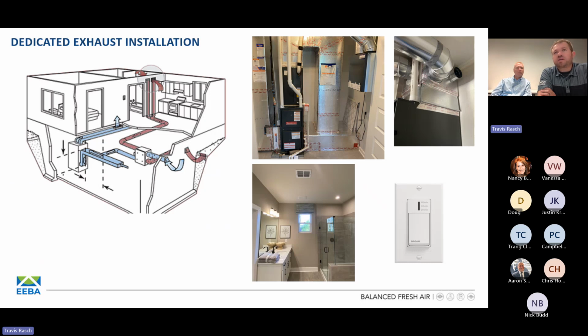A couple of real world pictures there in the upper right. In this case, you can see the ERV placed in the mechanical closet, mounted to the wall, with ductwork running into the return side of that air handling system. In the bottom left picture, we have a bathroom, and the register grill closest to the end is what's actually extracting stale air from that bathroom. In this case, there is what we call a boost switch or override switch that wires back, low voltage, to the HRV or ERV. You can push that switch to boost the unit to its maximum speed setting. Maybe you have it running at a low continuous speed, and then you hit that boost switch and it takes the unit up to its maximum CFM setting, ultimately trying to extract that humidity, that odor, etc., out of that bathroom as quickly as possible, and ultimately be a replacement for a typical bath fan in this type of situation.